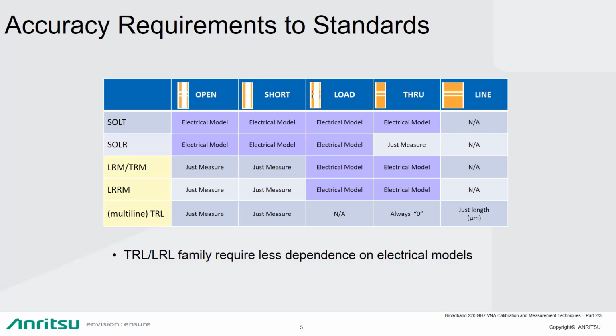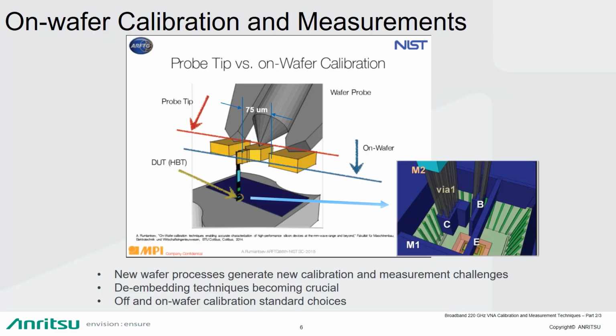So that gives us another way to look at these options that we have in performing calibrations on wafer over a very wide frequency range. This slide gives us another perspective on the challenges of calibrating probes. So when we think about calibration of the broadband system by touching down on cal substrate standards, we now start to think about the fact that those standards reside in, let's say, a calibration substrate, and that calibration substrate may not accurately reproduce where the DUT is located. So the environment of the DUT is quite different than the environment of calibration standards.